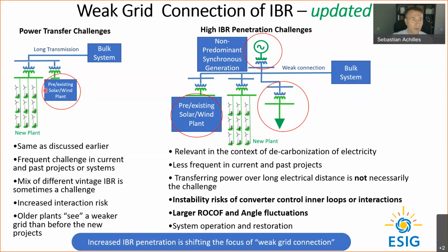What happens now more and more often is that you are doing this in a location where there are other plants. And when you connect a new plant, you make the system weaker for everybody. So interactions with this older equipment, in addition to keeping the system stable, is relatively common these days. And we continue to see the subject of connecting particularly large projects through long transmission lines. That is still there. Particularly, I think in North America, there's a trend right now of relatively large projects getting connected. Now, the other type of problems that we start seeing, I'm calling them here high inverter-based resource penetration challenges. Differentiating from the one on the left, in this case you have a new plant, but you're connecting it close to solar, batteries, not too many synchronous machines, loads, and all of this system is weakly connected to the rest of the system.